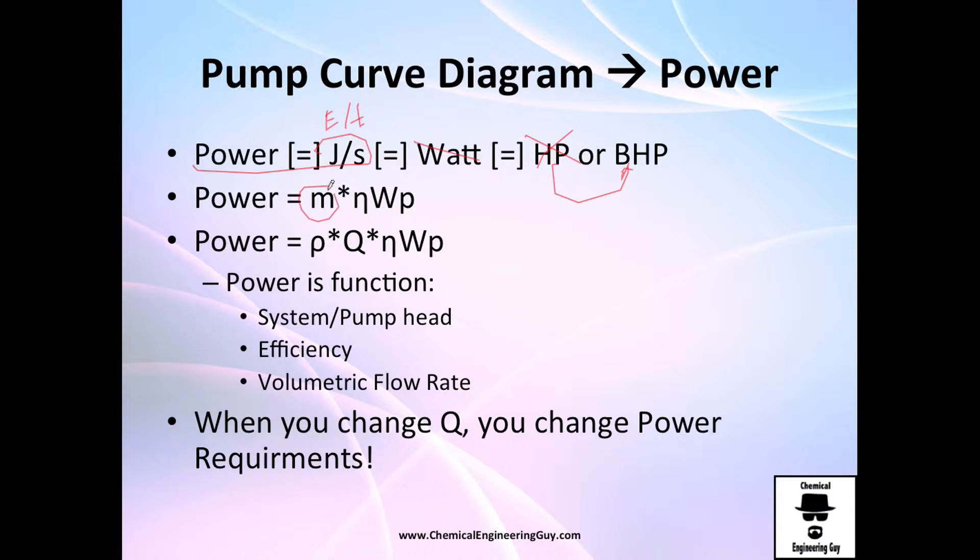Power comes from mass flow times the system head, or the pump head. Recall that we can calculate mass flow as density times volumetric flow rate, so therefore the power will be function of the system head, which at the same time is the pump head, and the efficiency of our pump, and the volumetric flow rate Q.